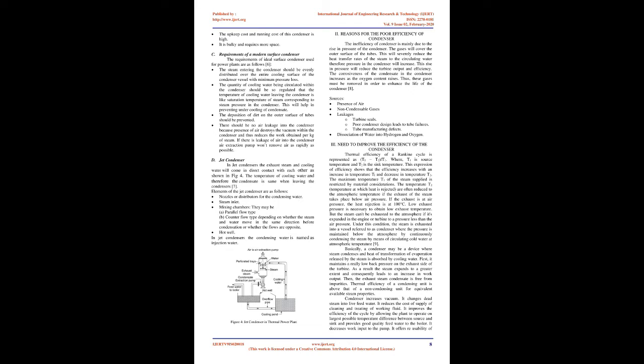6. The steam entering the condenser should be evenly distributed over the entire cooling surface of the condenser vessel with minimum pressure loss. The quantity of cooling water being circulated within the condenser should be so regulated that the temperature of cooling water leaving the condenser is like the saturation temperature of steam corresponding to steam pressure in the condenser. This will help in preventing undercooling of condensate.